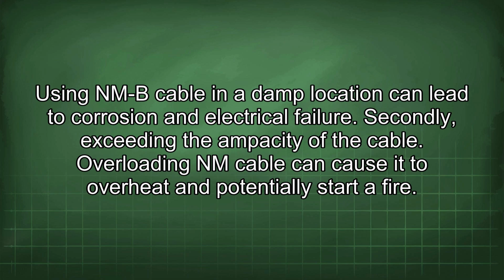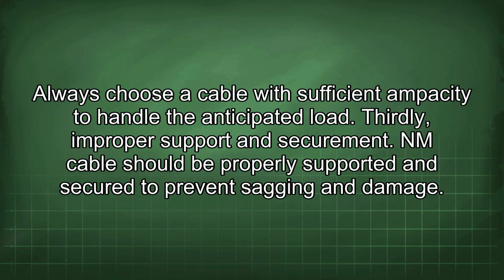Using an NMB cable in a damp location can lead to corrosion and electrical failure. Secondly, exceeding the ampacity of the cable. Overloading an NM cable can cause it to overheat and potentially start a fire. Always choose a cable with sufficient ampacity to handle the anticipated load.